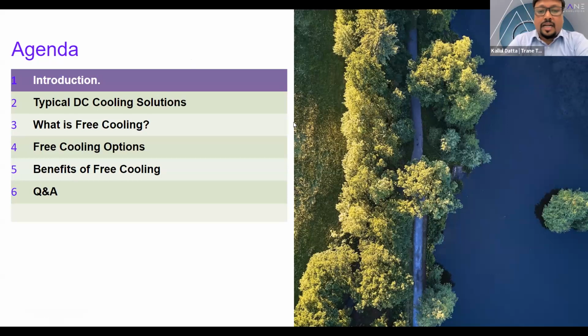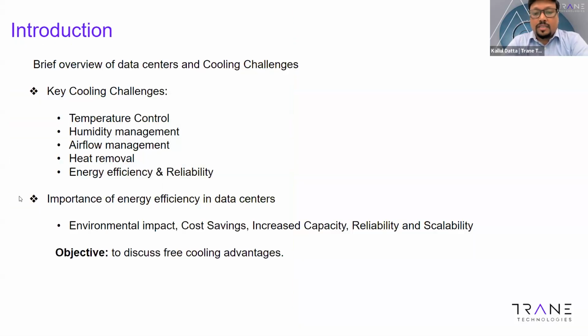There is data stating that data centers consume close to 1 to 1.5% of the global electricity, and out of that, cooling accounts for 30 to 50% of data center energy use. The average data center's power usage effectiveness is close to around 1.67. Cooling energy consumption in data centers is expected to double by 2025 or in the upcoming years, depending on the aggressive plans the data center players have.